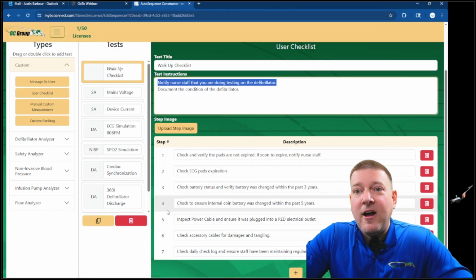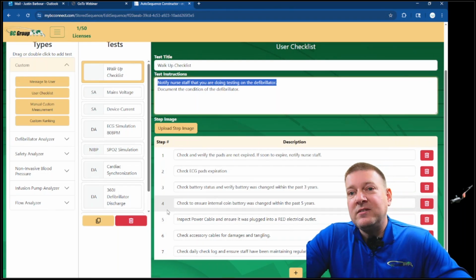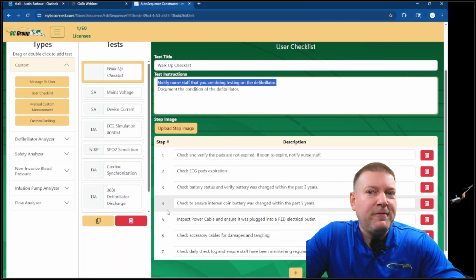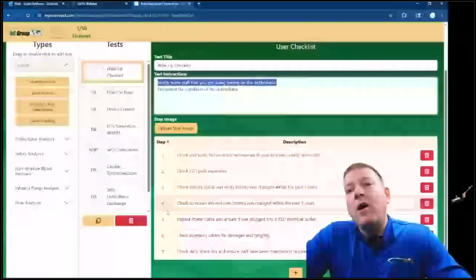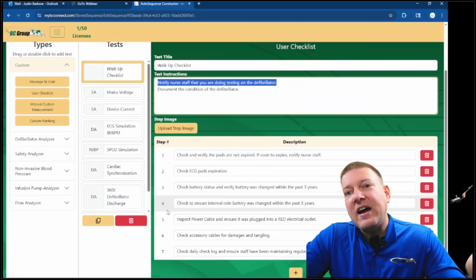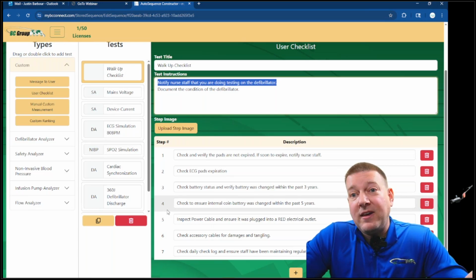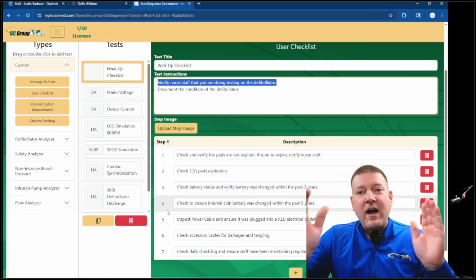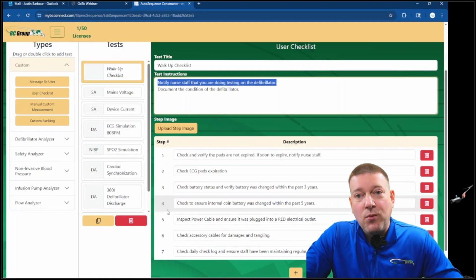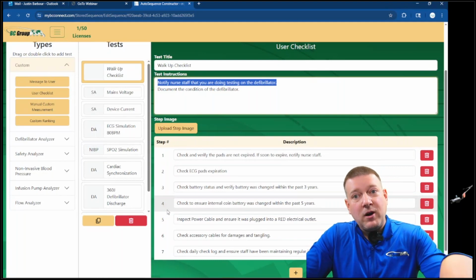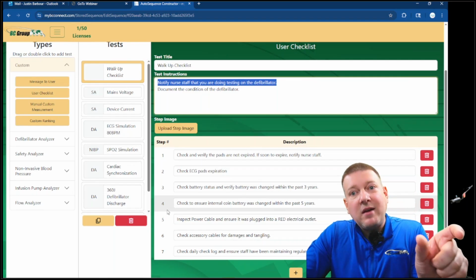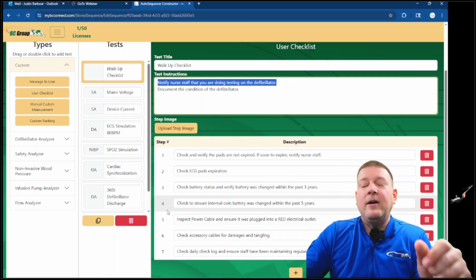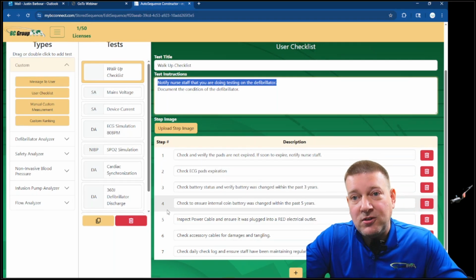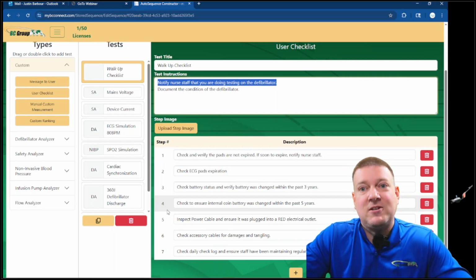That's why I have a walk-up checklist, and I also have a walk-away checklist, meaning things like: is the defibrillator plugged into a red emergency outlet? Are the cables stowed correctly? Are the paddles attached to the top of the defibrillator? Stuff like that. You can incorporate a photo of how you want it to look when they walk away from the device. I want the cables stowed in a very particular location, and I want the PM tag put right here in the front corner of the defibrillator. You can incorporate all that so the technician doing the work knows exactly what your expectations are.